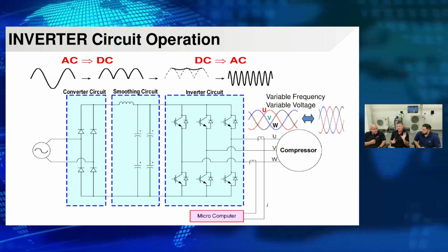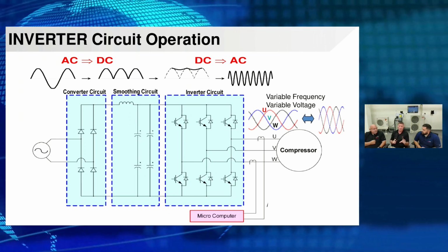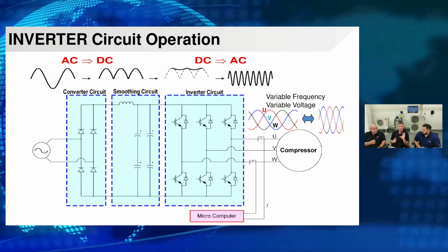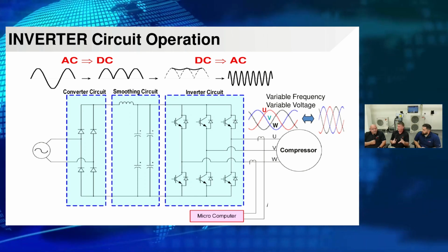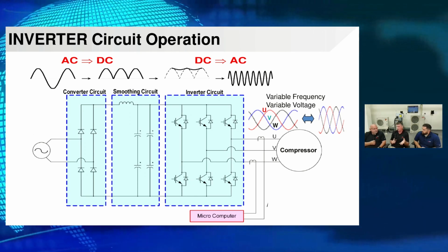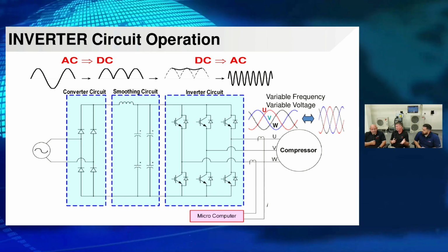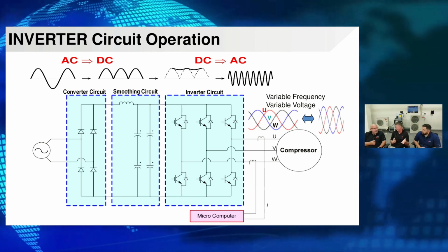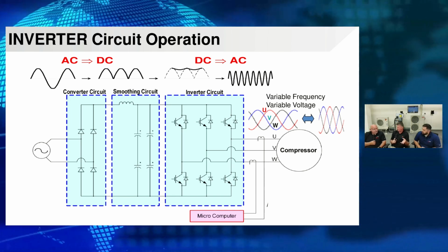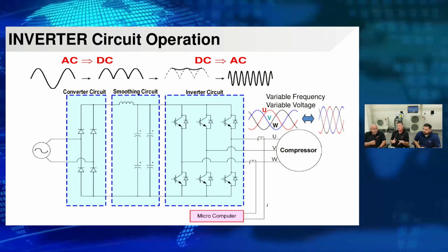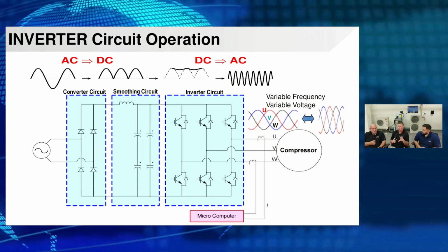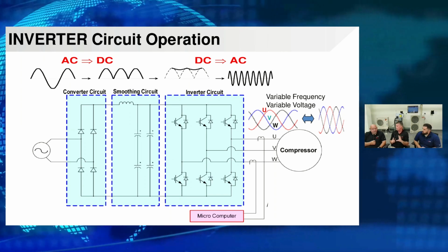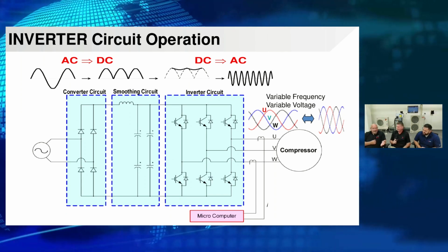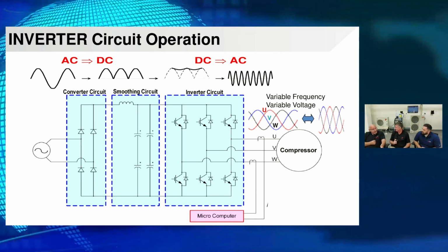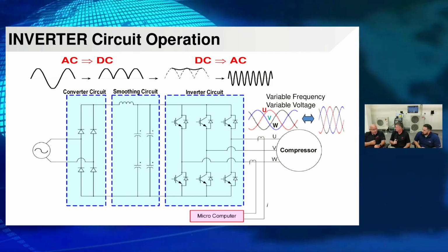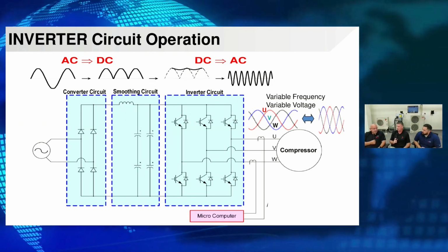But very rarely, and I think that's a thing to stress to people, the beauty of an inverter is that we're using a three-phase motor. Yes. We're not talking about a permanent split design motor that is going to fail on a leg if it has a component failure like a capacitor. Right. Three-phase motors rarely burn out. And so by modulating into a three-phase scenario, we get super long life out of these when installed and maintained properly. Right. And on top of that, when you're doing an electrical test on the compressor, what are you looking for? I should have the same resistance between the three of them.